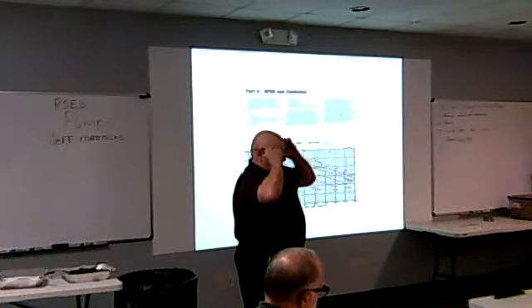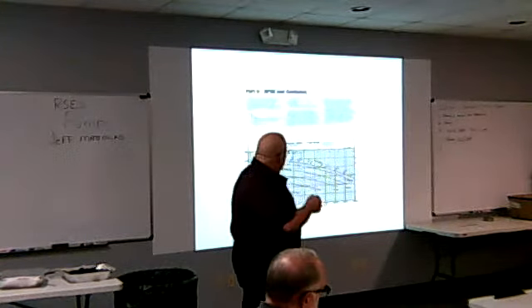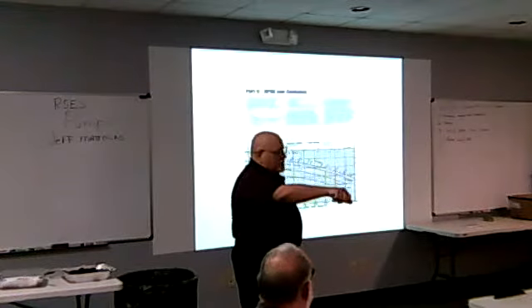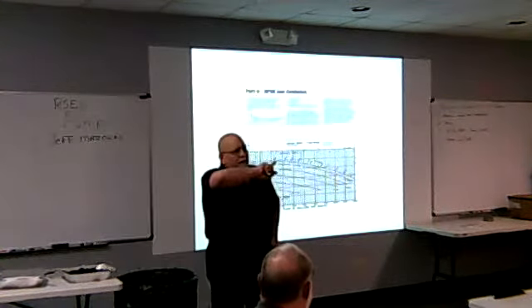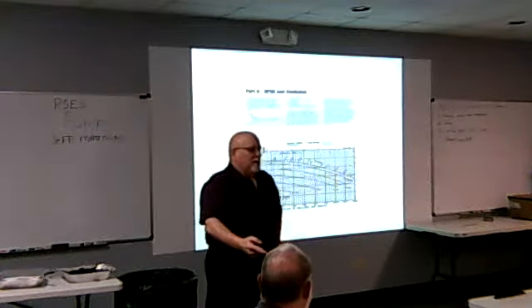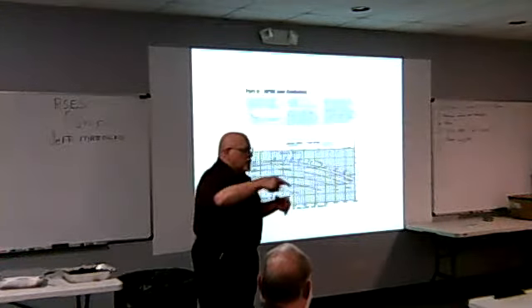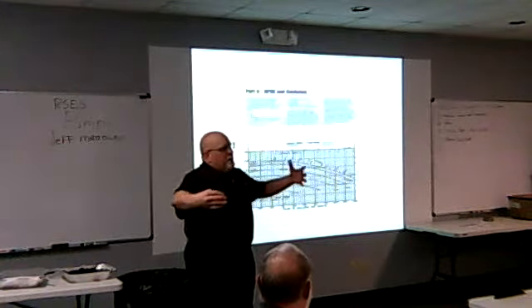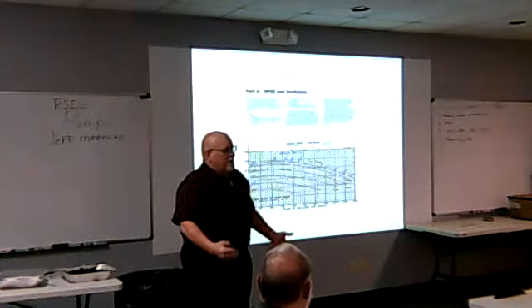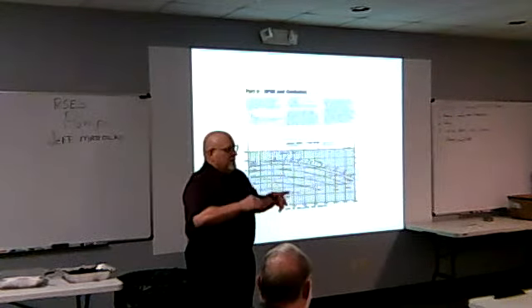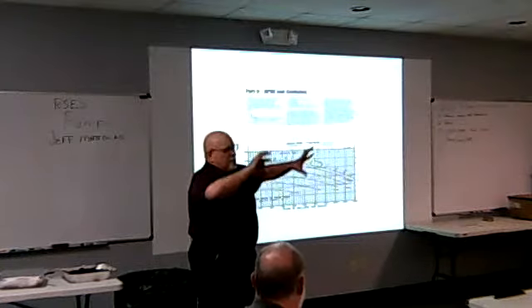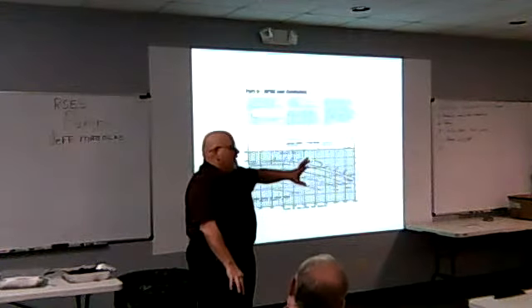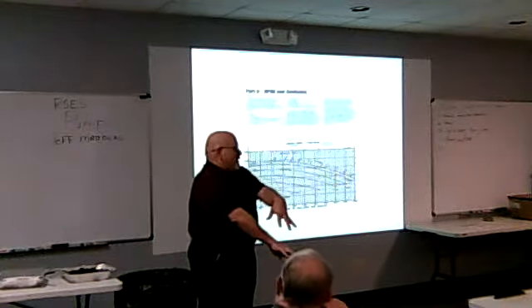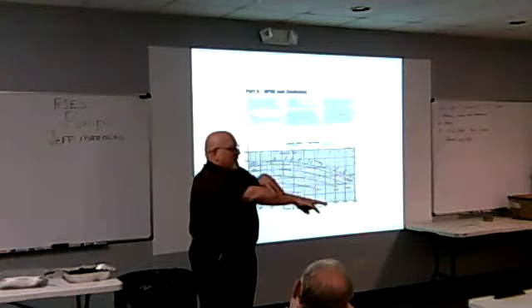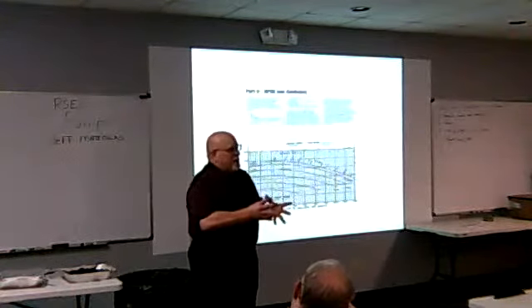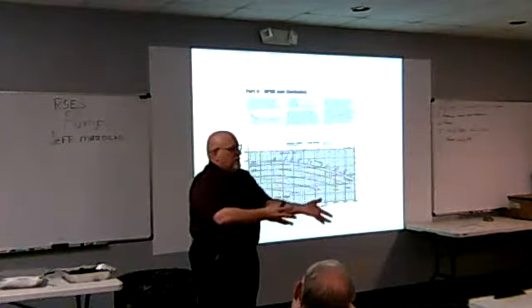It's way down. Exactly. But what will happen in the eye of your impeller, when you look at your impeller here, as the water enters the vanes of the impeller, it's under high pressure. When it goes through the vanes of the impeller, it reduces pressure. It speeds up, as in the Bernoulli equation. I have pressure here and velocity, my velocity goes up, my pressure falls. Well, now we're in our vacuum chamber. What's happening to our water in the eye of that impeller? I don't have enough positive pressure there, it boils.